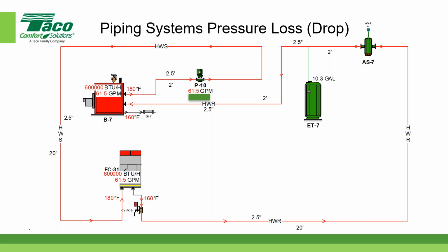So 4 feet per 100 and 6 to 10 feet per second are only a starting point. You need to see the ASHRAE charts. I think that's something you and I should agree on. For today's discussion, I oversimplified the problem. If we went through ASHRAE, we could manipulate the design so that it would comply with our 8 feet per second and 4 feet per 100 feet. But ASHRAE gives us much more in the way of guidelines in terms of what we should select.